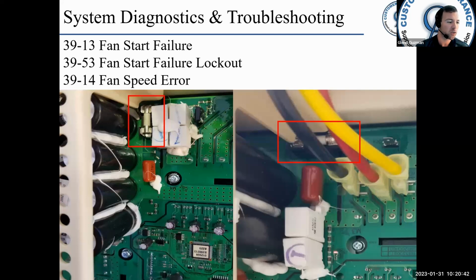If you're getting these faults, inspect the wiring, the connectors, look for damage, loose connections, overheated connections, check the fan blade, make sure it spins freely, check the external fuse. If no voltage, if no physical blockage is present and the fuse is not open, ohm the motor and replace it if necessary. Now, 3914 is a little different.